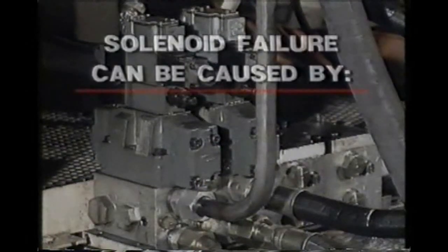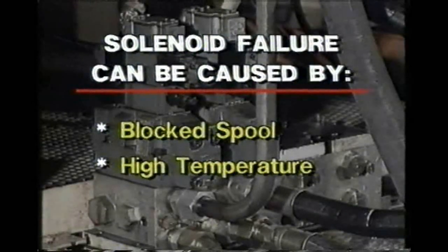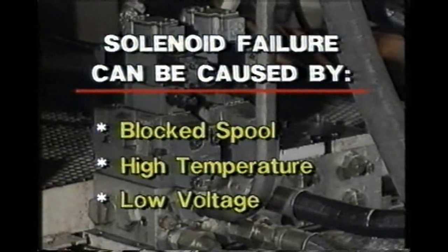Solenoids sometimes fail, and when they do it's usually because of blockage of the spool, because of high temperatures around the solenoid, or because of low voltage.